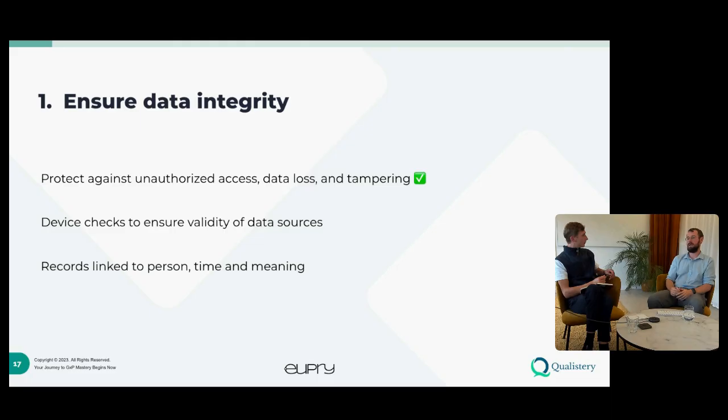Examples that I've seen of systems that were not really compliant are where there was some record, some data, and then there was a signature, but it did not say what that signature meant. It was basically putting your name on a piece of paper. It was not "I did review this" or similar.